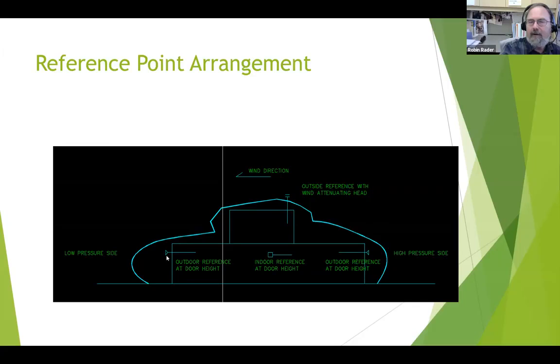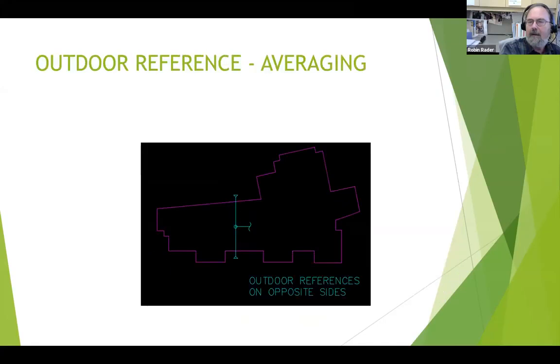This is a picture of another outdoor reference. One thing that can be done is you can average one sensor on one side of the building with another sensor on the other side. However, during wind, the two pressure relationships don't actually equal each other. And so your average doesn't really fit exactly. This is just a plan view of a two pressure averaging system.